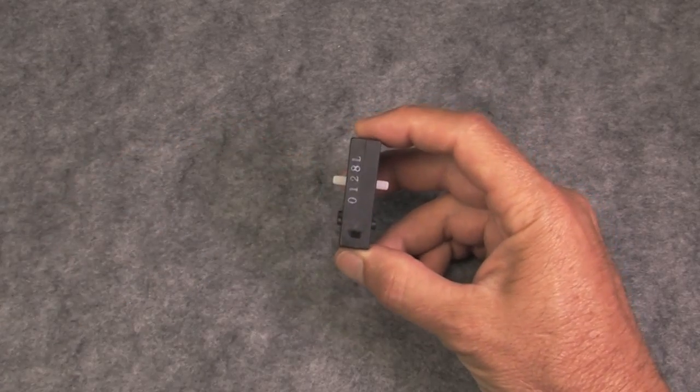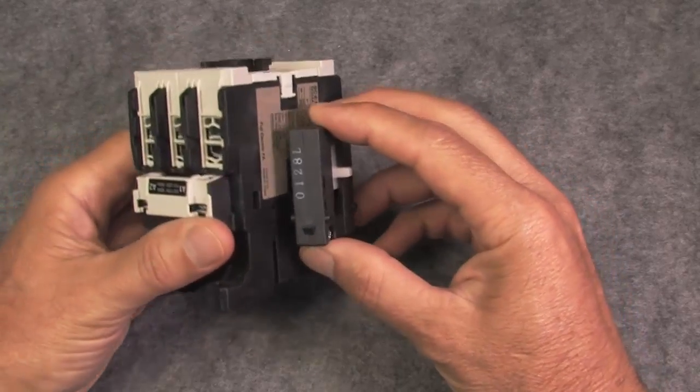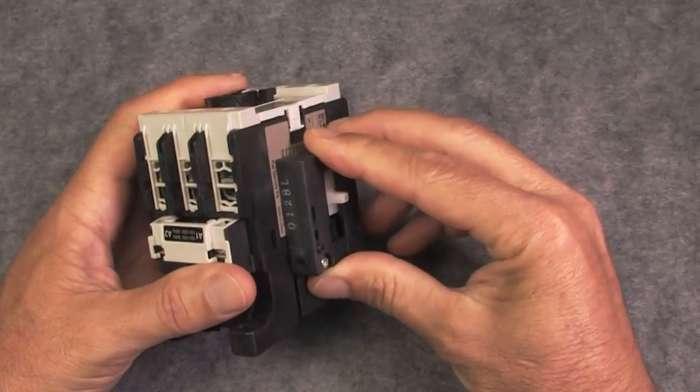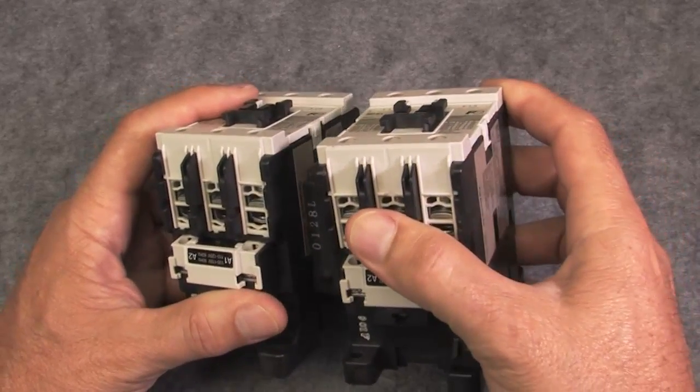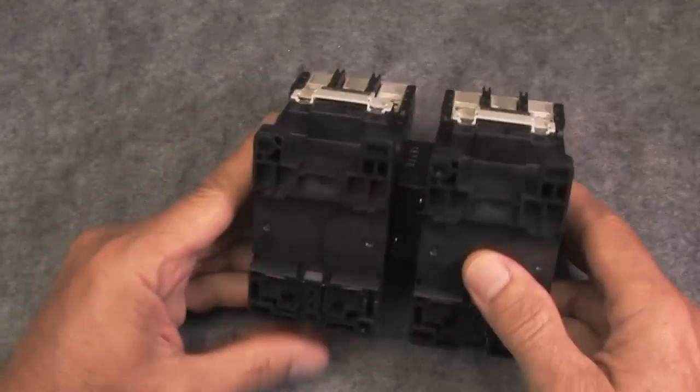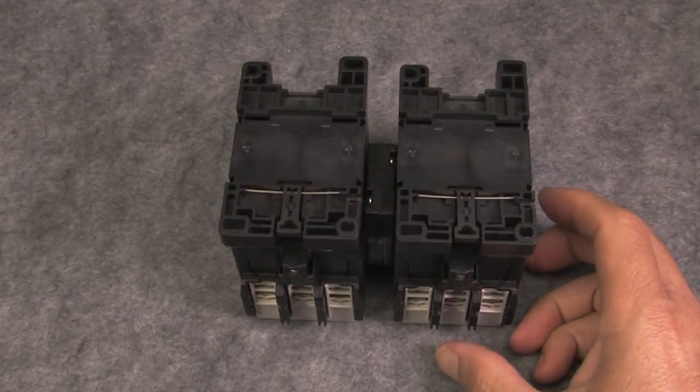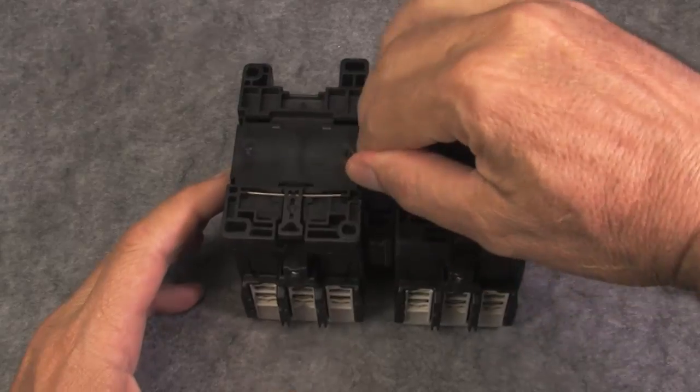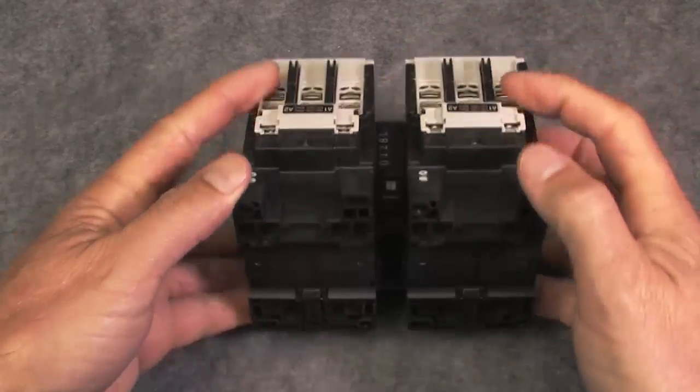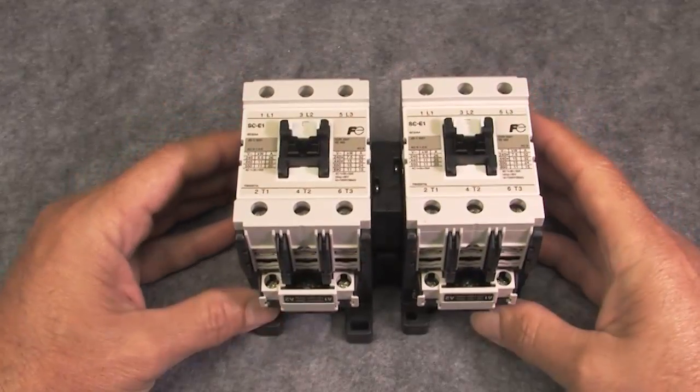If the coils energize at exactly the same time, the two sides will bind and neither will activate. But the odds of that happening are slim because usually one slips ahead of the other. To install this mechanical interlock, you just insert it between the two contactors.